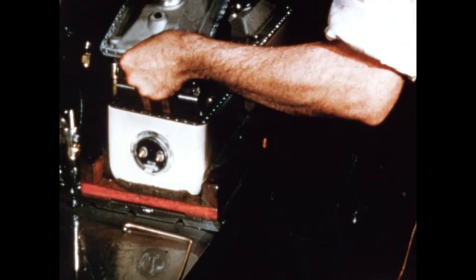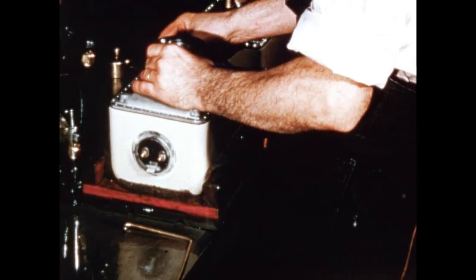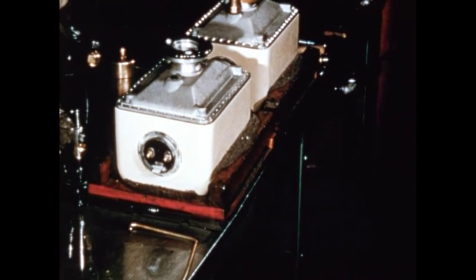Perhaps the most intricate assembly job in the Weber plant is the X-ray head transformer, which contains the X-ray tube immersed in a special insulating oil, which protects operator and patient against electrical shock.